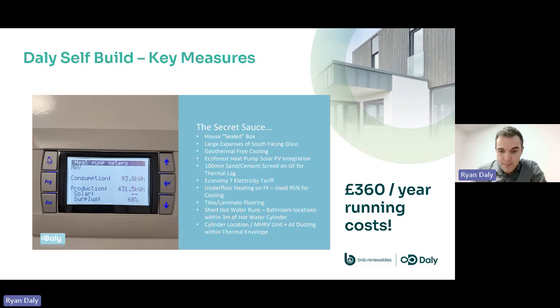Underfloor heating is used primarily on the ground floor. It's only used about 5% of the year for heating upstairs, but it's used the majority of the time for cooling in the summer. With the cooling, we find that it works best when you have hard surfaces. So all our flooring is tiles or laminate flooring, which works really well. Carpets would inhibit that cooling effect slightly. So that's the reason we went with that type of flooring.